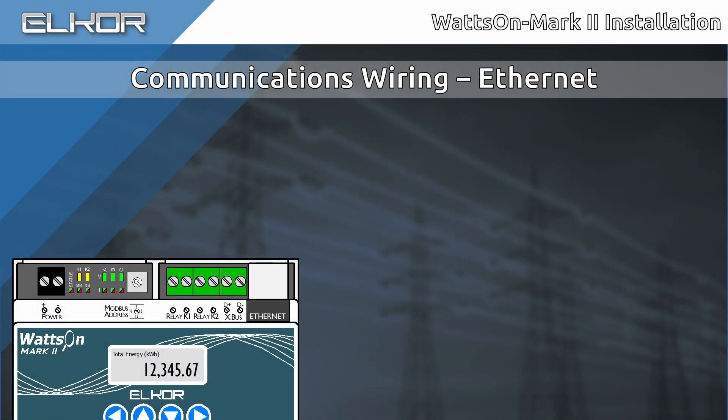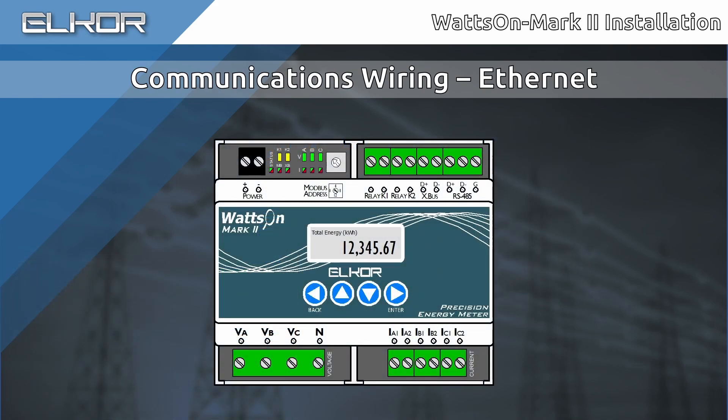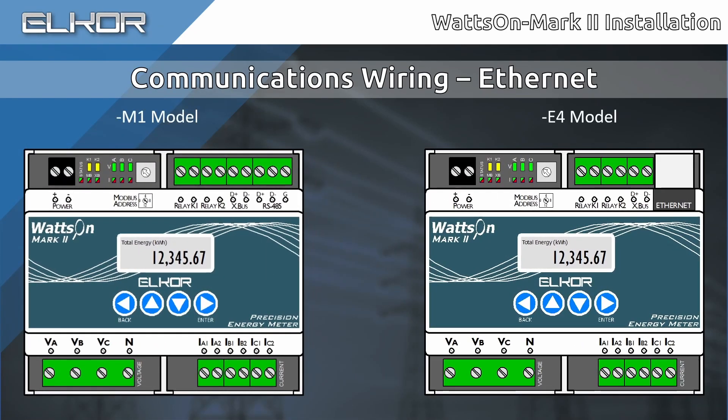If using the E4 meter model, Ethernet connection is straightforward. Using a quality Cat5e or higher patch cable, connect the meter to the network. While the meter may be directly connected to a PC for configuration purposes, in most cases it is connected to a switch or a hub. Advanced network configuration is out of the scope of this video, but check out our support site for more resources. Note that the E4 model of the meter replaces the RS-485 port with the Ethernet jack. Therefore, it is not possible to use both RS-485 and Ethernet in this configuration. If this type of connection is required, contact Elkor for some options.